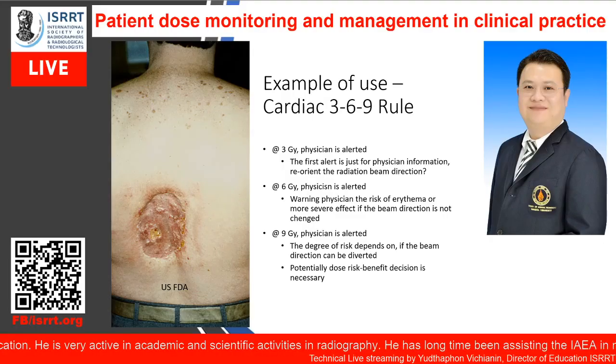examination. The thing is, if we monitor the dose, we know how much dose the skin patch has already received. If the patient has to come back, the physician would know he or she needs to angle the X-ray tube in different directions so that the dose won't be added too much into the same region. That's the thing. So in fluoroscopy, we monitor two things. First is stochastic risk, for which we monitor dose area product. And we monitor deterministic risk, or skin reaction, so we monitor the skin dose.